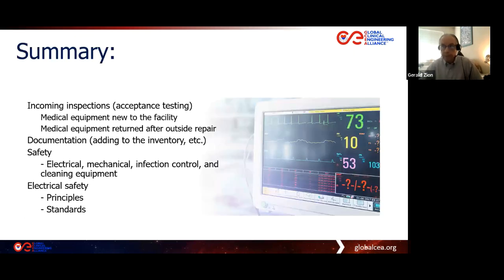All right, so in summary about medical equipment QA, we want to be sure we're managing incoming inspections, doing the acceptance testing, both when the medical equipment is new and when the medical equipment has gone away from the hospital for repair by someone else and been received back. We need to do another test and inspection. We want to document everything, and make sure we have that documentation either appended as PDF files or something in our inventory management system. We want to ensure there's safety for electrical, mechanical, infection control, and that includes cleaning the equipment. And we want to make sure that we're following the principles and standards for electrical safety that come to us from the international standards.